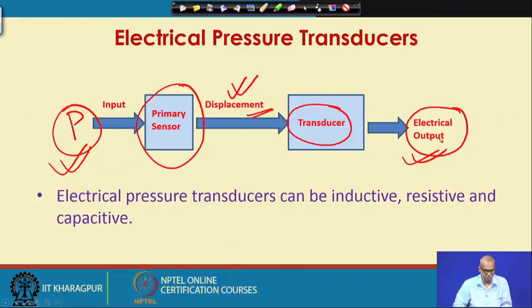of electrical pressure transducers. Now, electrical pressure transducers can be inductive, it can be resistive, it can be capacitive or it can also be piezoelectric type. We have talked about transducer elements in detail. So, we will briefly touch upon these inductive, resistive, capacitive and piezoelectric pressure transducers. So, the basic idea is to make use of an electromechanical transducer to convert the displacement output of a pressure gauge to an electrical output.